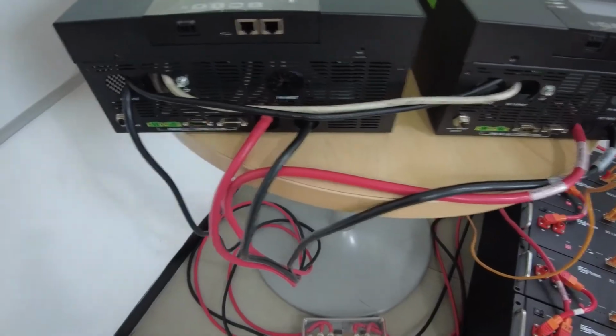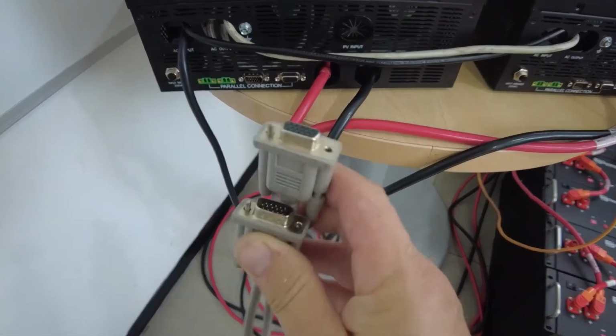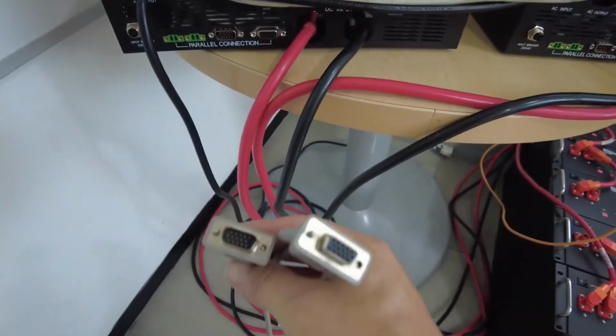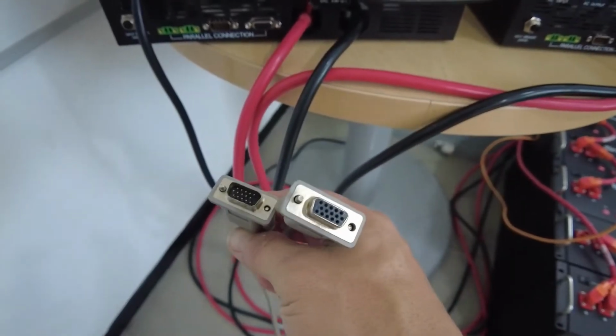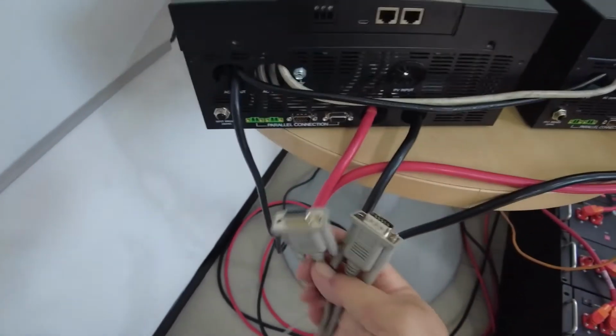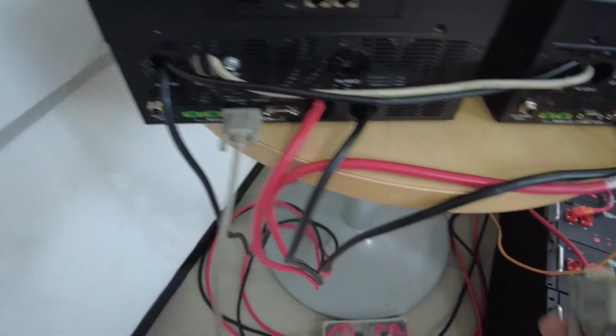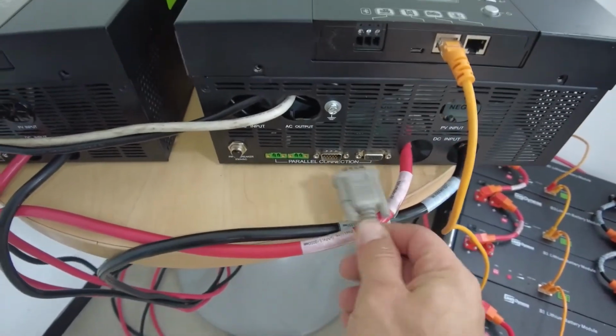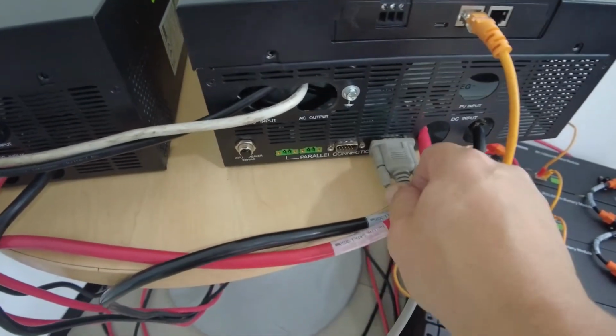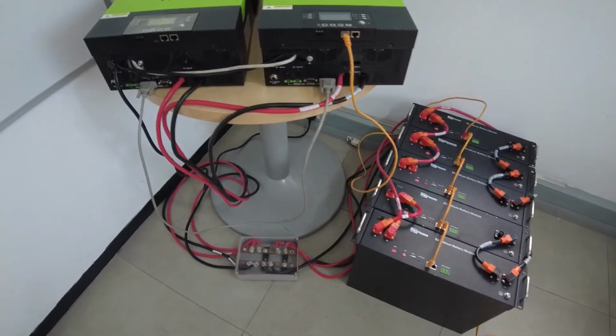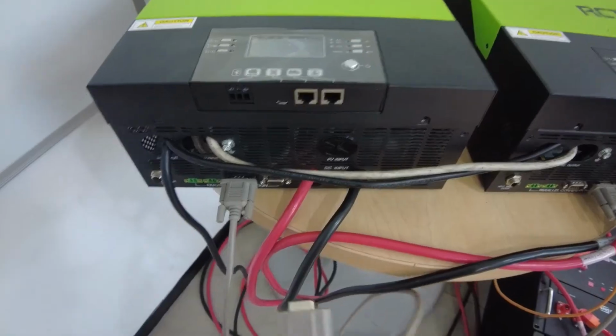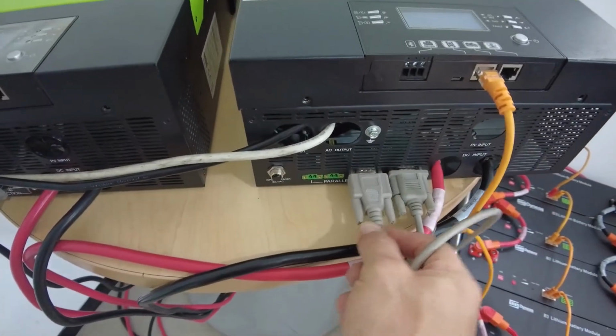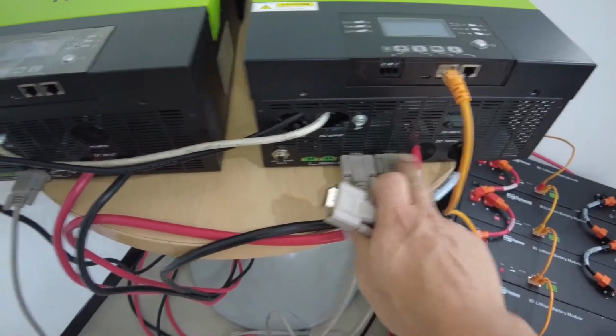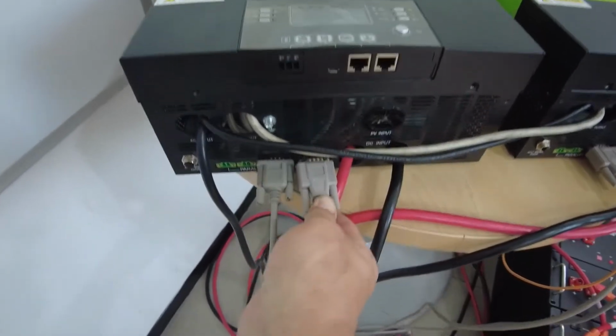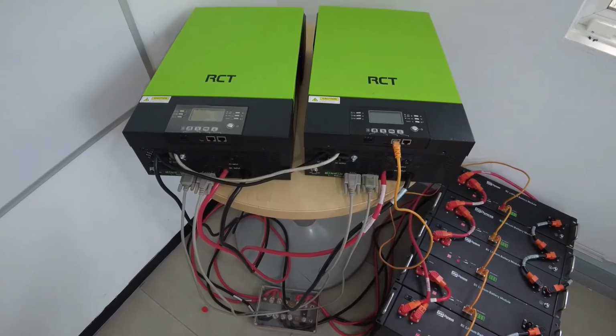So the syncing cable that we have here looks like a VGA cable, but the difference is it's male to female. Now when you have two inverters, it's fairly easy to connect. You'll connect one side of the cable to the port it fits on, and then the second cable to the one it fits on over there. Then your second pair of cables you'll connect. So in this case, your two ports far from one another will be connected, and then the ports close to one another are connected. Okay, the syncing cables are connected.